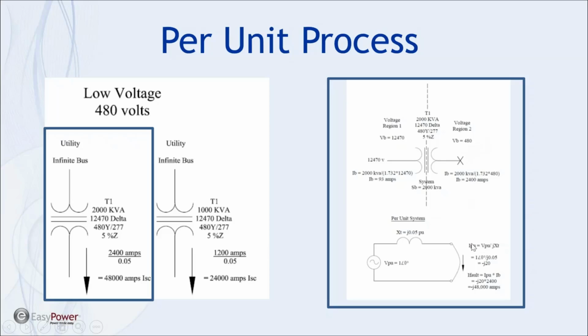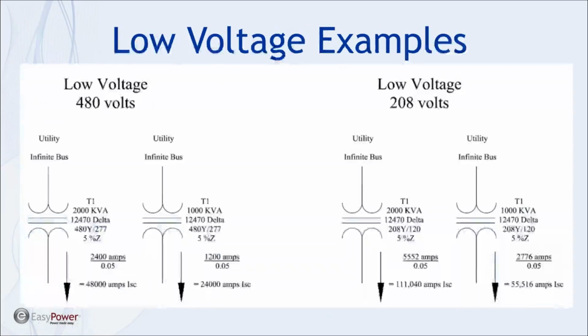So now I go back to my 480 volt region with my J20, multiply it by the base current of 2400 amps, which in this case, when we have a simple, single transformer, also matches the rated current of the transformer, which I really didn't explain back here, but that's where those numbers come from as well. So we don't have a very complex system, we just have a single transformer. So I end up, on the 480 volt side, with my 48,000 amps.